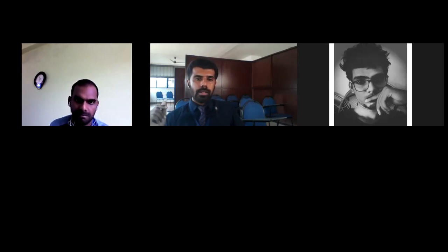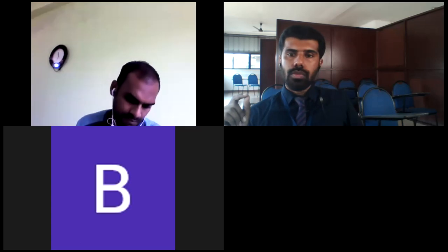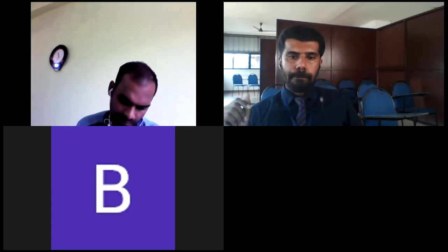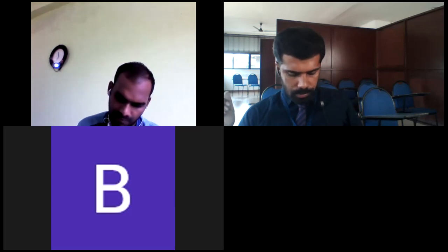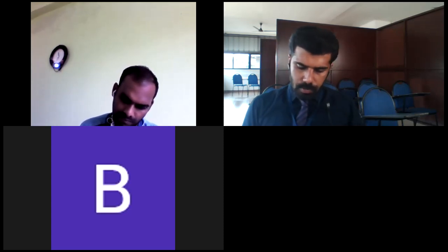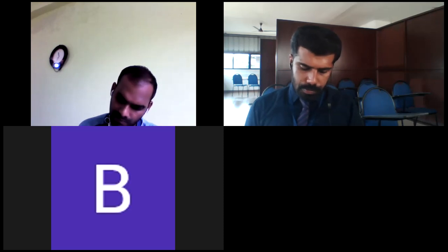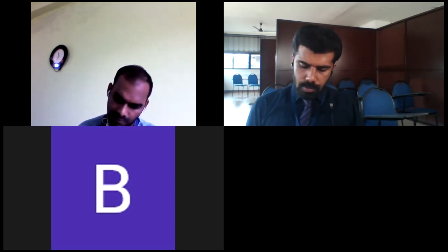So in that thumb rule that we gave yesterday, you just include this also: 125 to 150 square feet. Usually, it will be giving 1 TR. It's only a rule of thumb, okay?